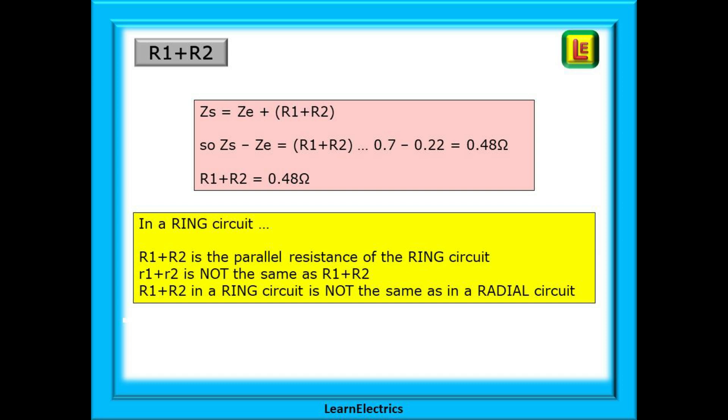We're talking about big R1 and big R2 here, the parallel resistance in a ring circuit. And in a moment we will use this to calculate little R1 and little R2, the end-to-end values of a conductor. Note that R1 plus R2 in a ring circuit is not the same as R1 plus R2 in a radial circuit. This is very important.